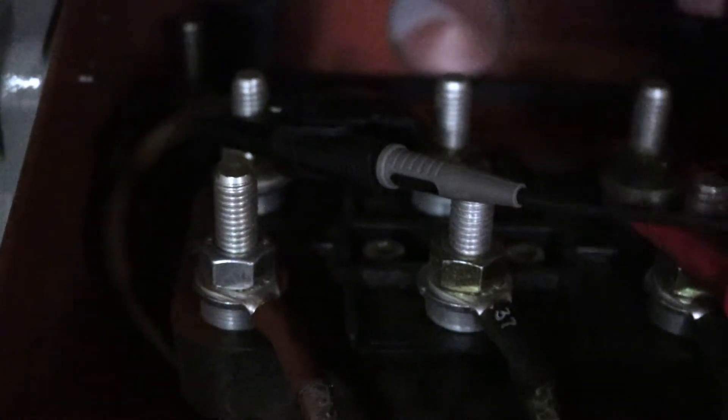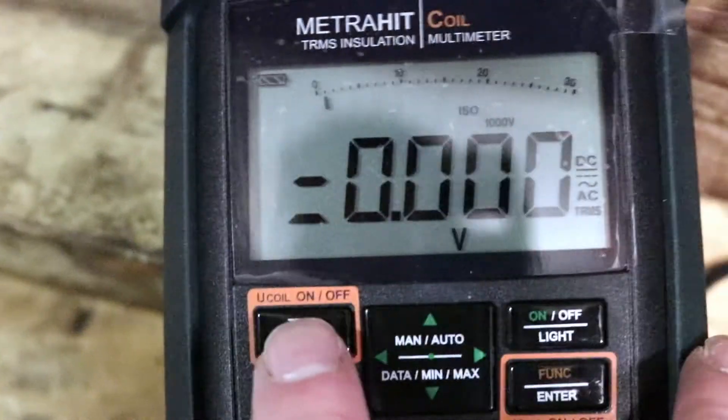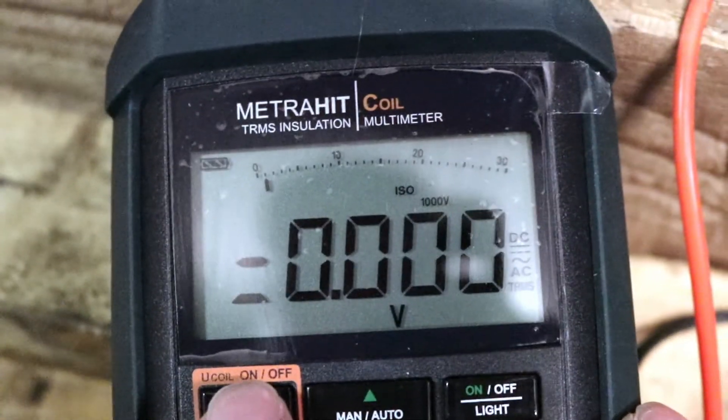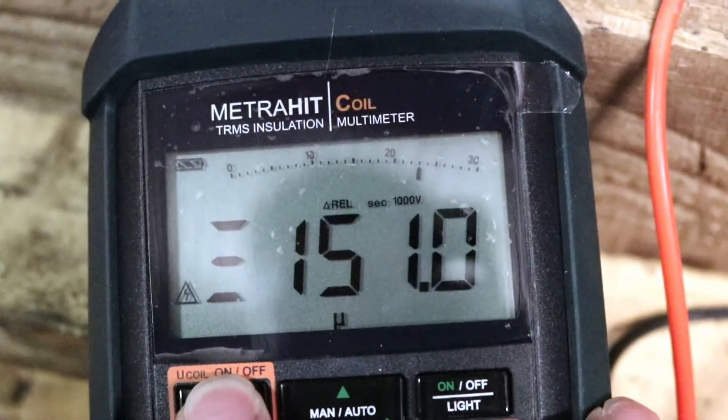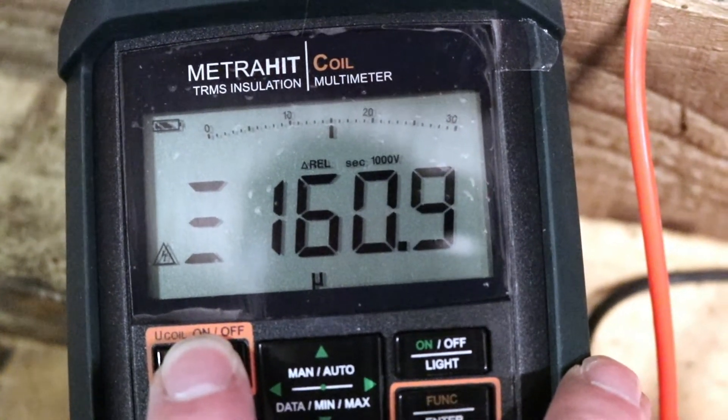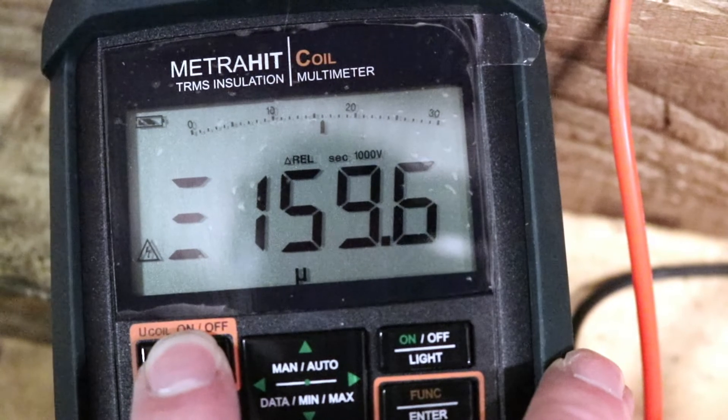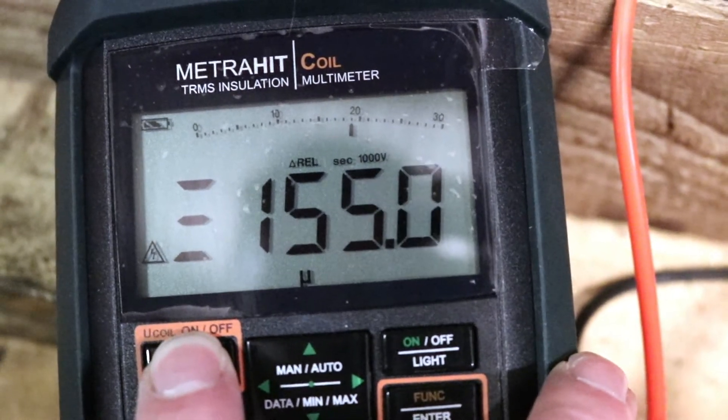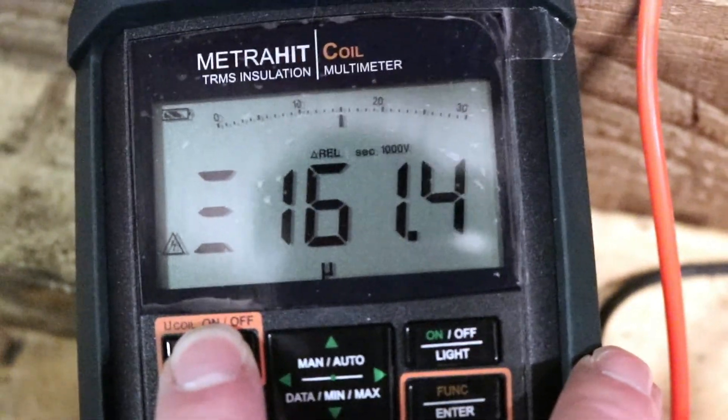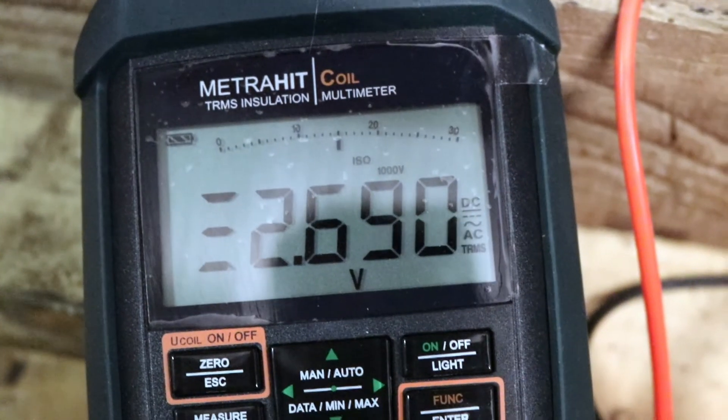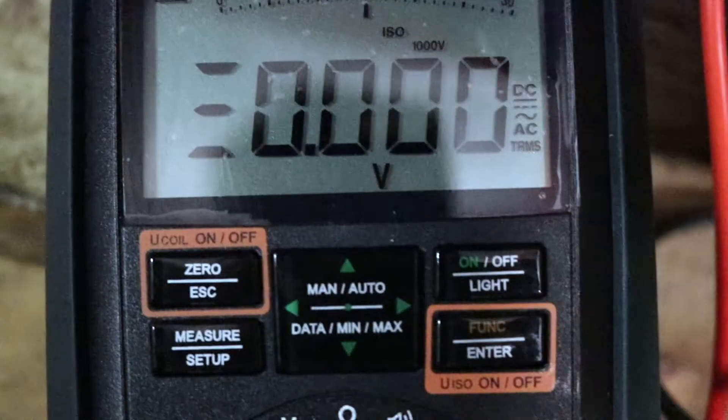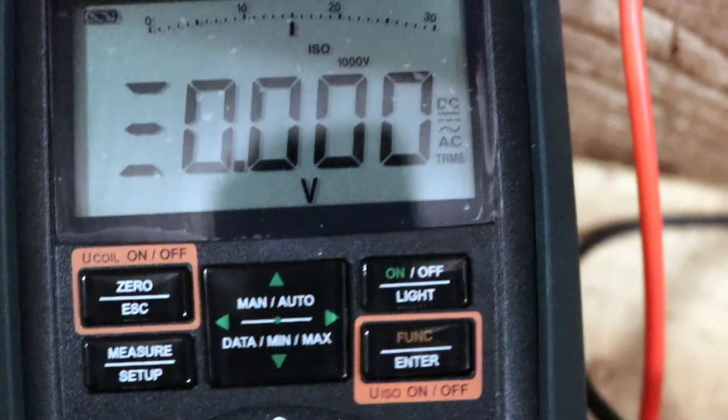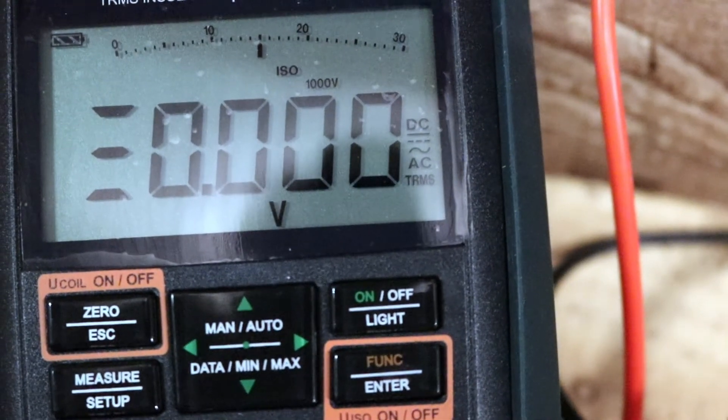And the final winding will be W. I'm not sure we'll cut over there and up over onto the last one. So final phase reading. 150. And you can see the differential jumping around. Discharges. Differential of 15%, which is indicating an inter-turn fault.